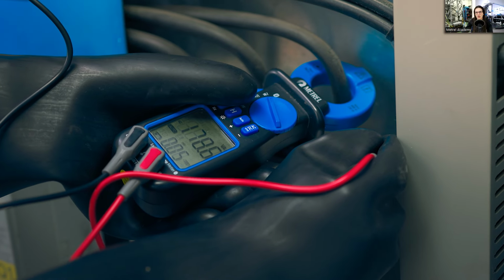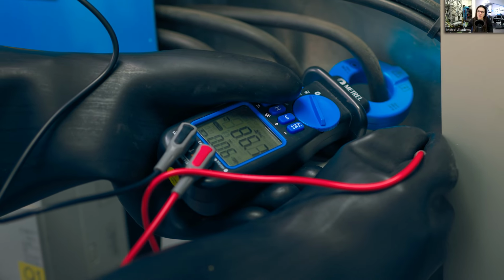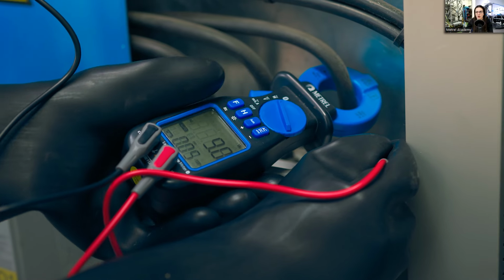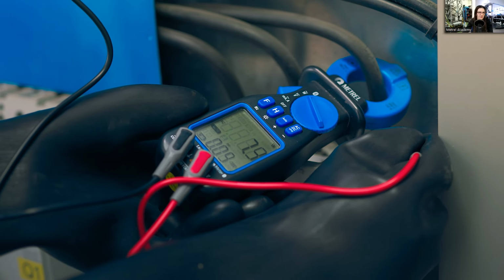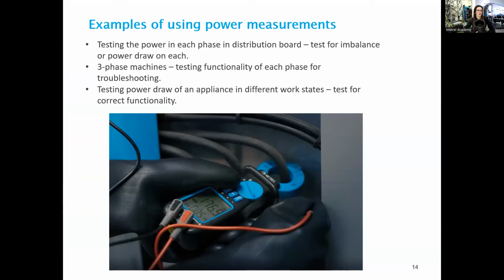Again, different functions of the clamp can be used to narrow down our result and to look for other possible problems. So, some examples. As I already mentioned in the video, we look for imbalance or a power draw between the three phases in the distribution board. The imbalance can be a very serious problem in the installation if it reaches more than about 2%.